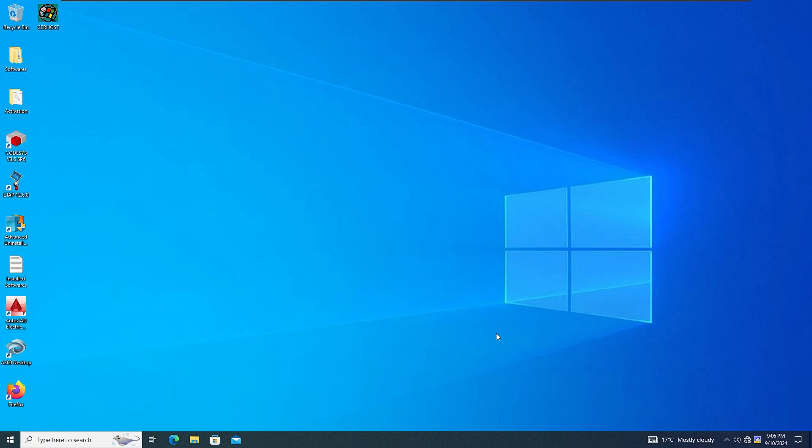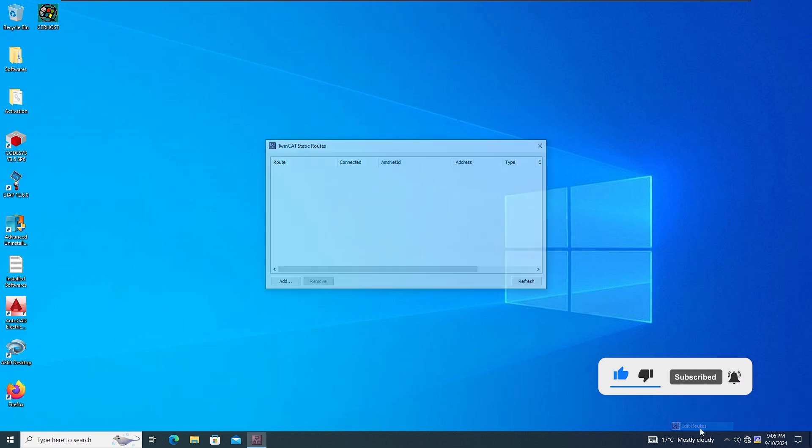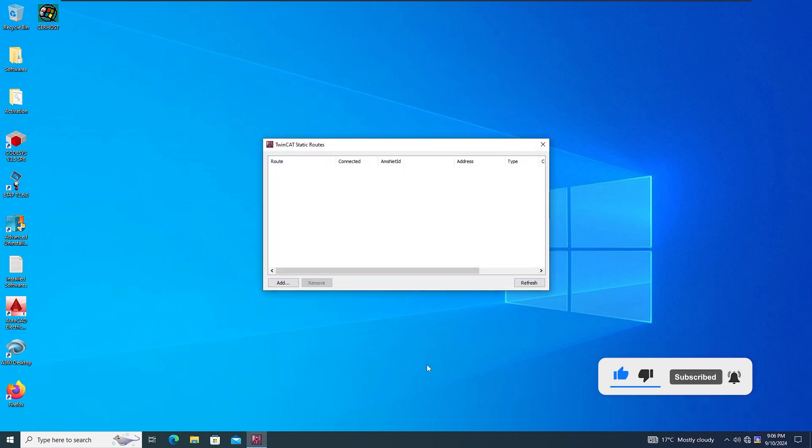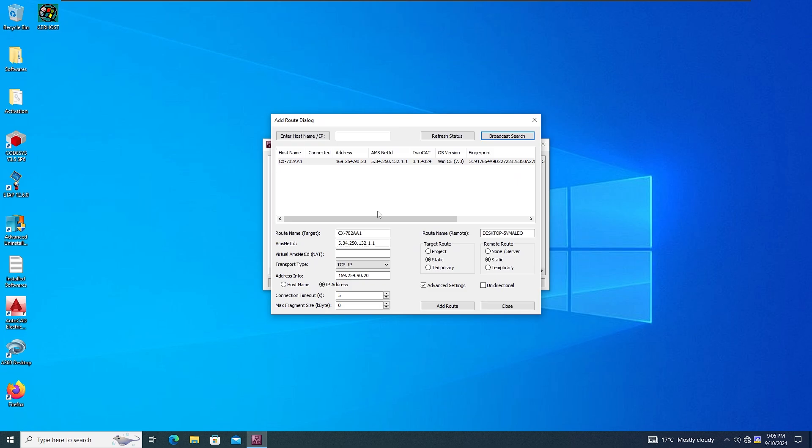To get connected to the PLC you need to have the XAR installed on your computer. After you do the installation you see this logo, so you can go to Edit Routes. In here you need to add the IP address of your PLC if you know it, or you can do a broadcast search and it's going to find it for you. This is the PLC that I've got connected. It has Windows CE embedded into it as well and that's the TwinCAT version.